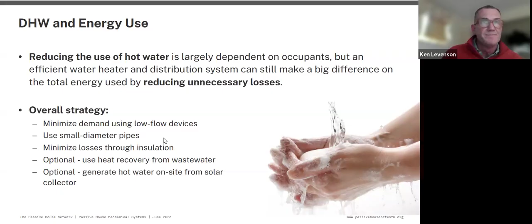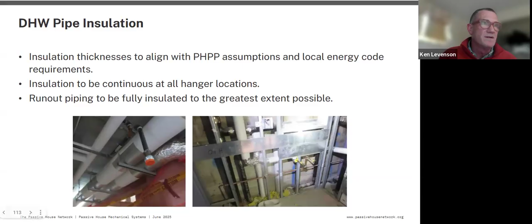This is where passive house goes a bit rigorous-crazy with the piping of the domestic hot water. We really want this to be continuously insulated, those hot water pipes in particular—no breaks, we don't want the hangers breaking the insulation, we don't want any interruptions as much as possible. So you see nice and clean installation.